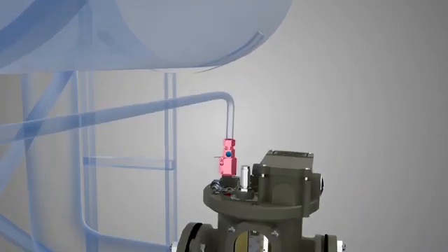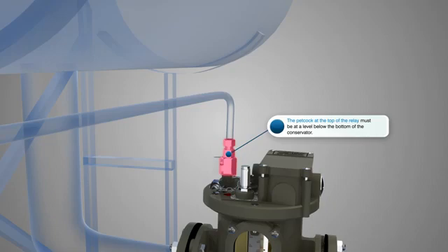The petcock at the top of the relay must be at a level below the bottom of the conservator.